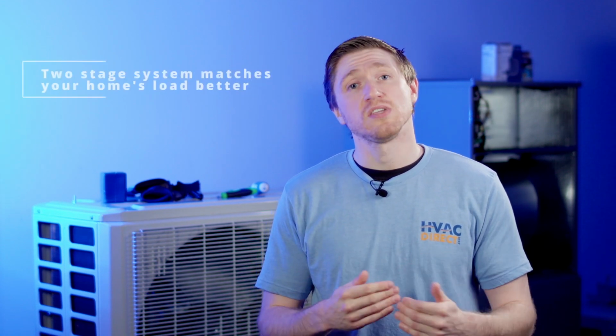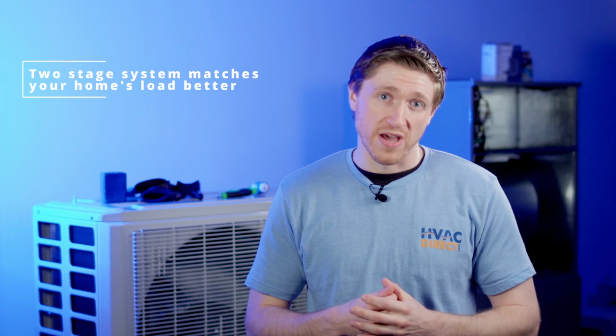If we're going to dig a little deeper into it, the two-stage system also will match the load better for your house. Whenever we size air conditioning systems, your contractor should do what's called a Manual J, or a load calculation. They'll figure out exactly how many BTUs you need to remove an hour.